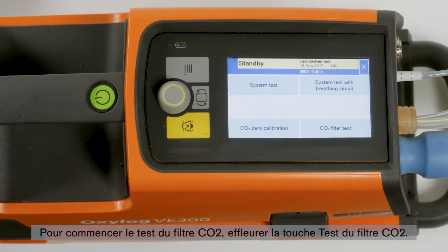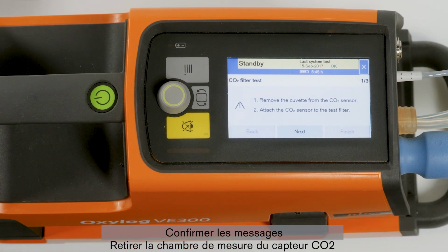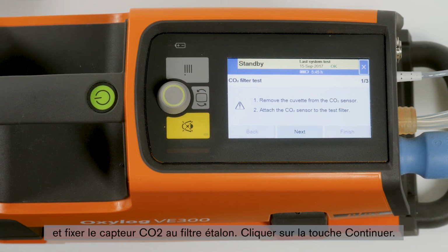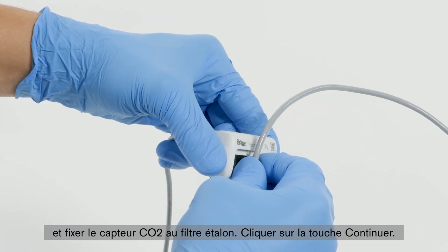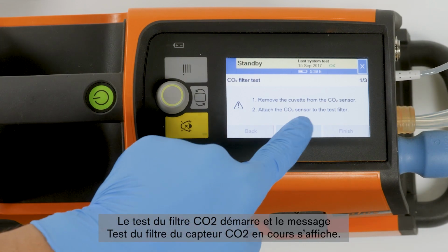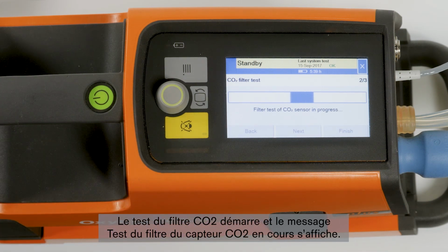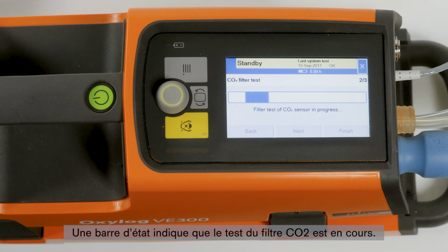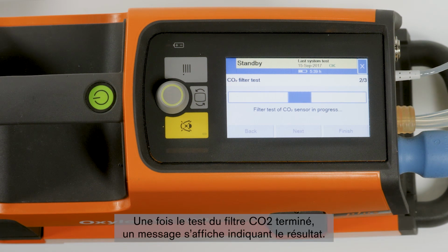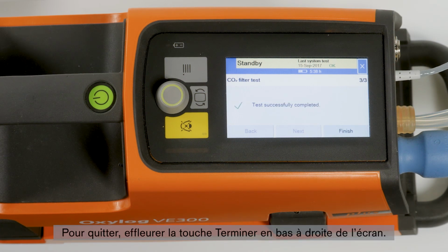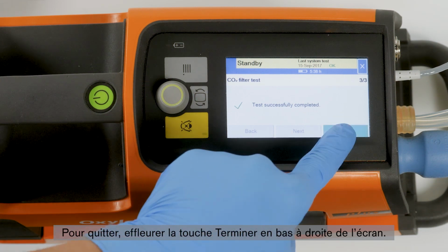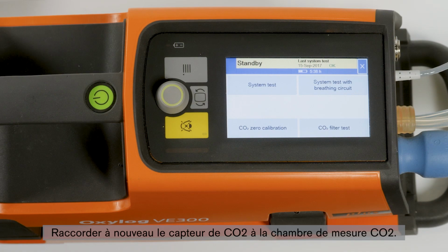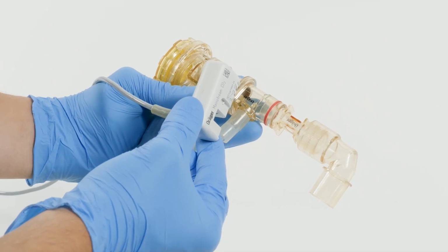To start the CO2 filter test, touch the button CO2 filter test. Confirm the messages, remove the cuvette from the CO2 sensor, and attach the CO2 sensor to the test filter with the next button. The CO2 filter test starts and the message Filter test of CO2 sensor in progress is displayed. A bar indicates that the CO2 filter test is in progress. When the CO2 filter test is completed, a message is displayed indicating the result. To exit, touch the Finish button in the bottom right-hand corner of the screen. Reconnect the CO2 sensor to the CO2 cuvette.